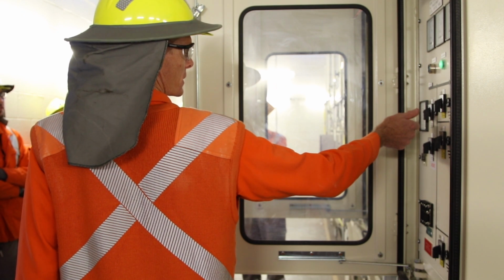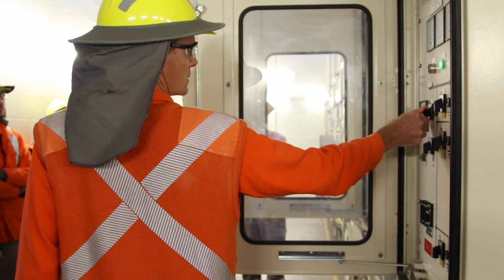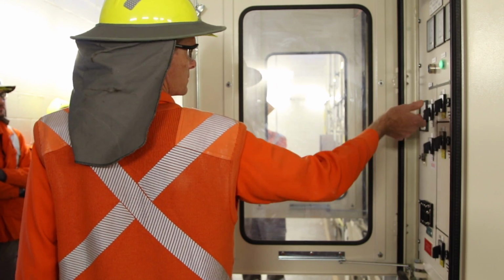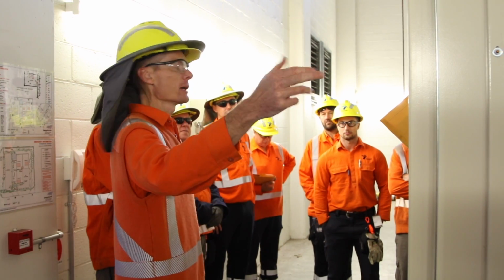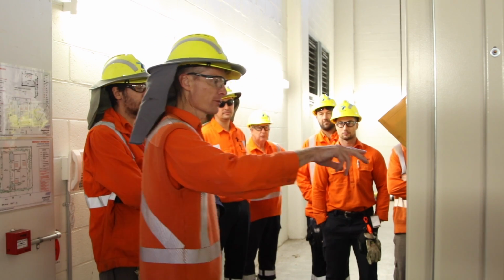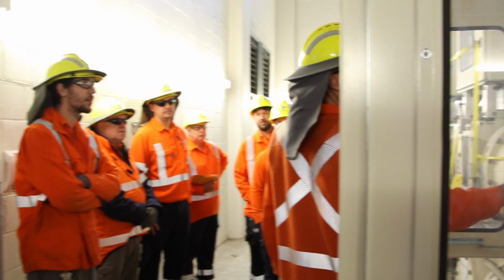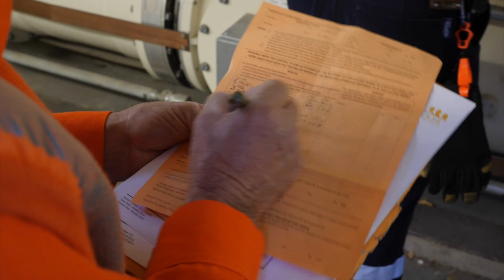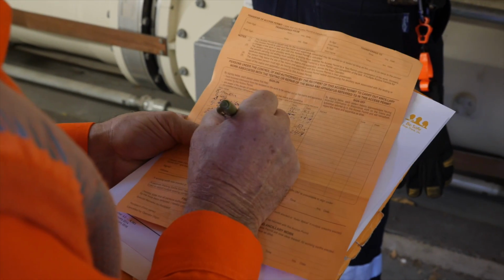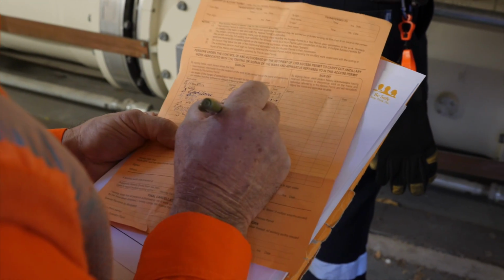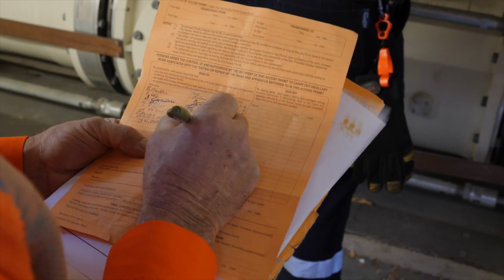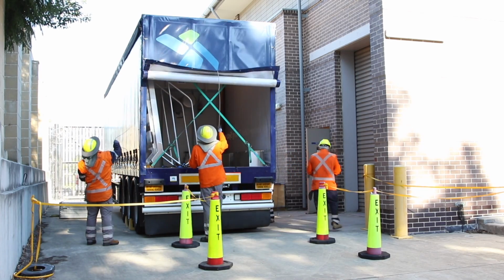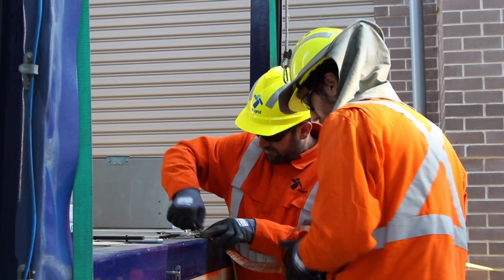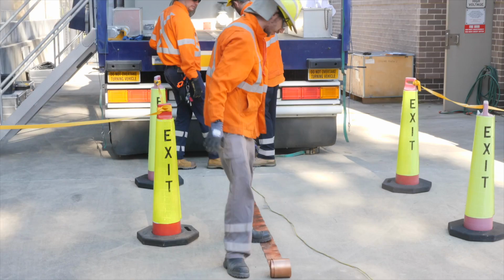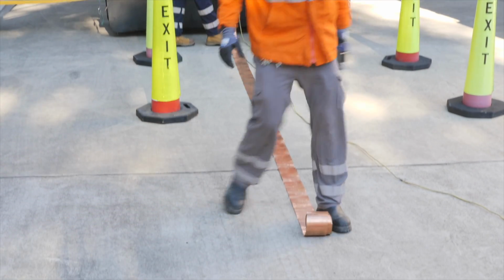Before testing begins, the GIS must be switched and the earths removed to allow testing. Once the access permit is verified, the physical isolations and earthing are checked on-site to be correct. Once the checks are complete and the access permit recipient is satisfied, the permit is discussed with the work group and they sign on. Earthing is the first thing to be connected onto the trailer at the beginning of setup and the last thing to be removed when packing the trailer away.